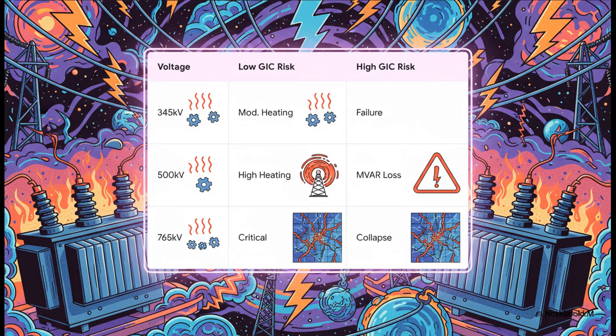To make our grids more efficient, we've steadily moved to higher and higher voltage networks, from 345 kilovolts up to 500, all the way to 765 kilovolts. But those higher voltage classes drastically increase our geomagnetically induced current vulnerability. Under a high GIC impact, a 345 kilovolt transformer faces severe heating and failure. A 500 kV unit faces extreme reactive power loss. And the 765 kV giants become a critical threat that can trigger total system collapse. Our very pursuit of efficiency has actually amplified our risk.